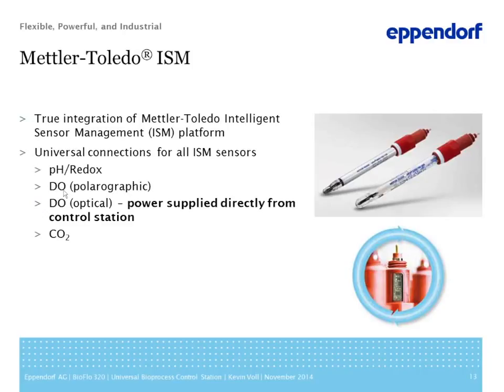This gives us the ability to provide universal connections. In the past, these connections were always dedicated. The analog circuitry required for pH or DO could not be combined into one technology. With this platform, we can now offer a sensor connection that is flexible between any of the major feedback sensors that the market needs: pH, redox, dissolved oxygen, carbon dioxide, all now available from one sensor port.